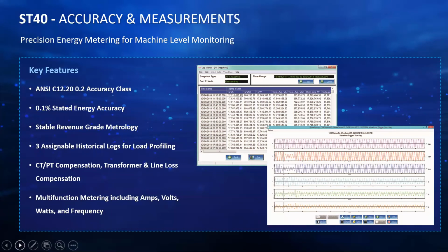Coming to some of the technical key features of the ST40. This is a 0.1% stated energy accuracy, and it is certified to the ANSI C12.20 0.2 accuracy class. It has 3 assignable historical logs for load profiling, and this is very customizable, I should say. So you can actually go in and set up into the meter how you want those 3 logs to be assigned. So you could set the first log for voltage and current, you could set up the second log for energy, you could set up the third log for power quality.